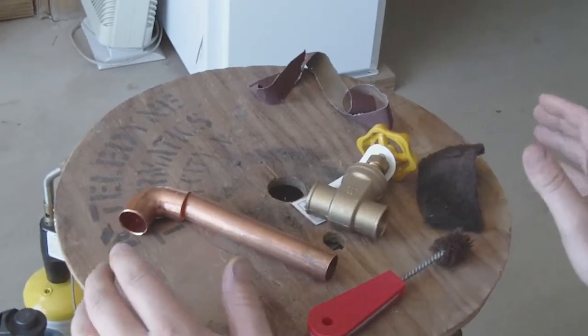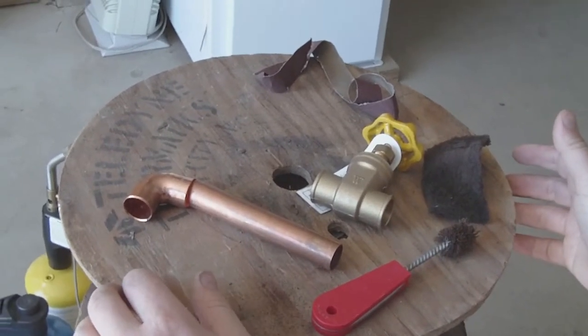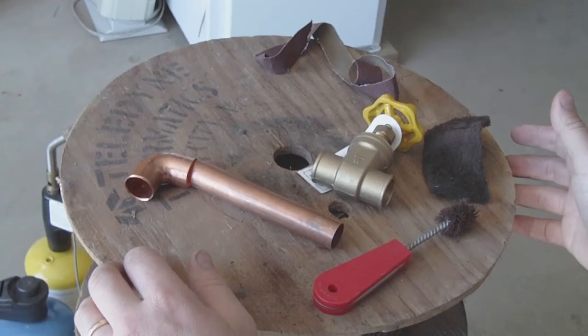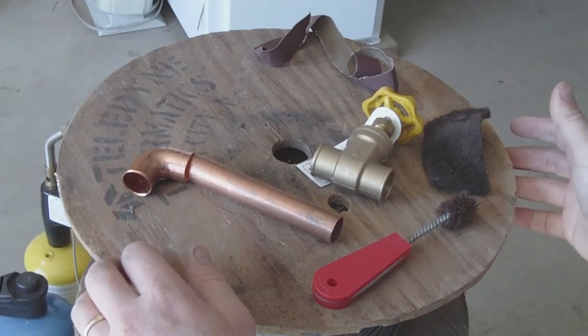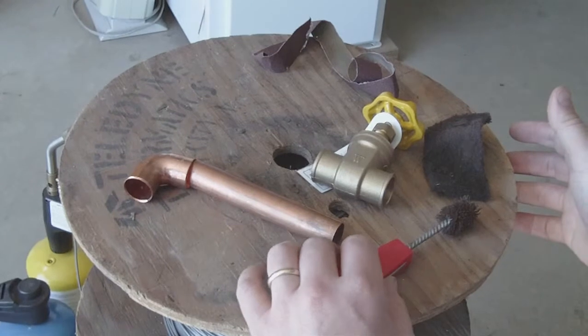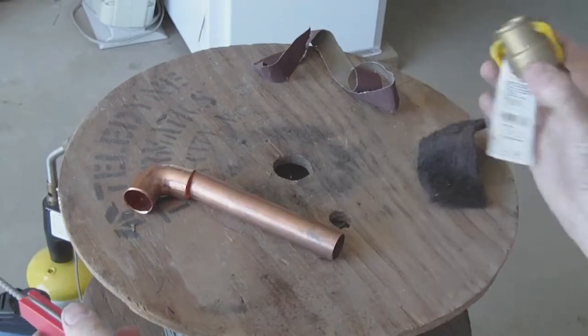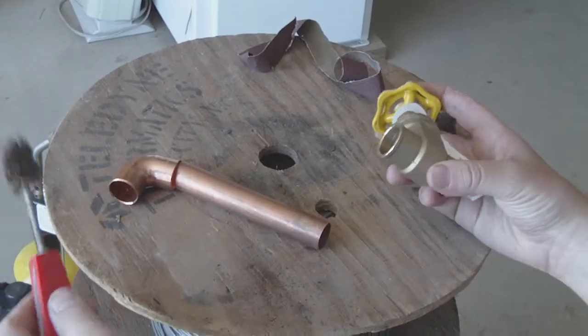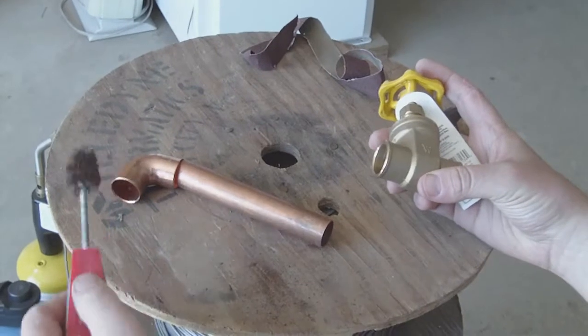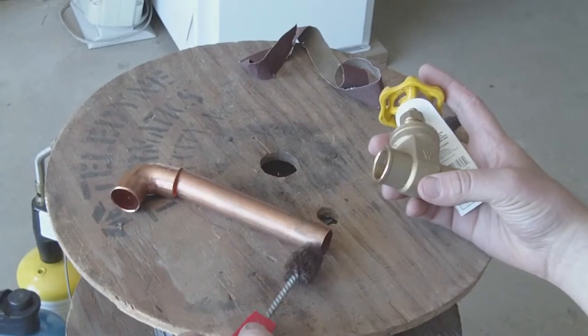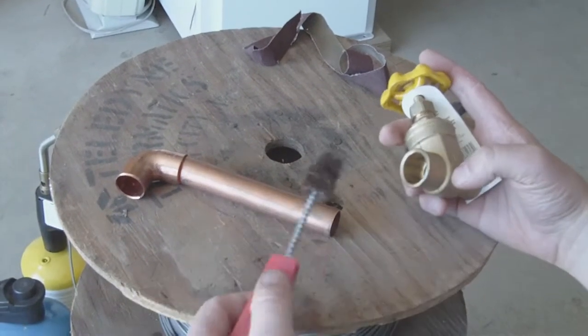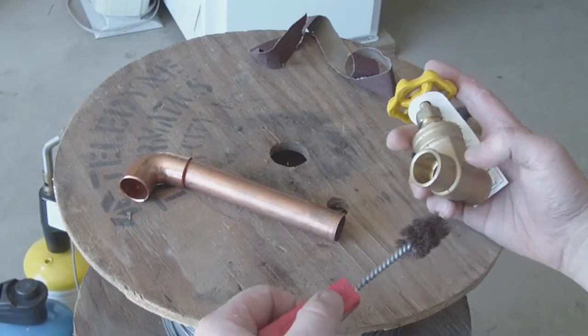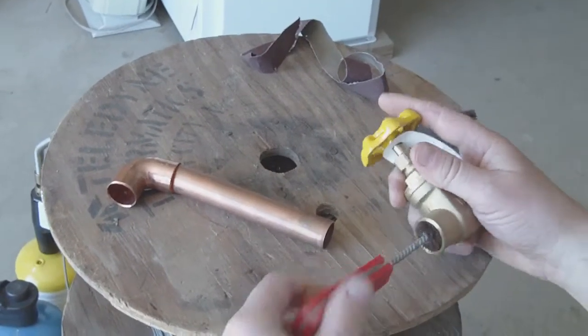We have now measured our pieces and it's time to clean the copper and the valve in order to prep it for the sweat solder. The absolute most critical component of making a successful solder joint is the cleanliness of the fittings before they get sweat soldered. If there's any corrosion on any piece, the flux and the solder will not adhere to it and will have problems.